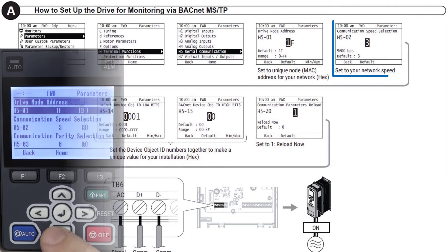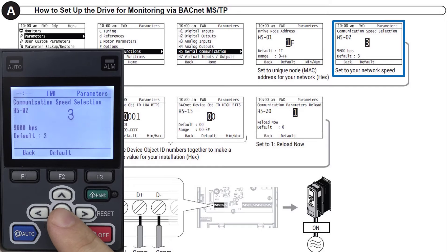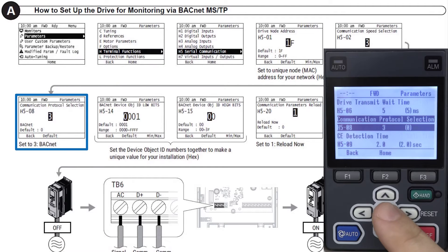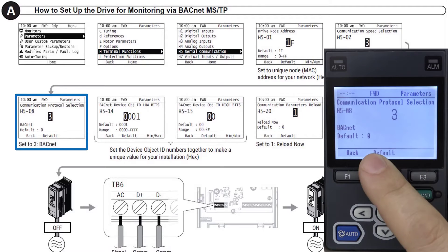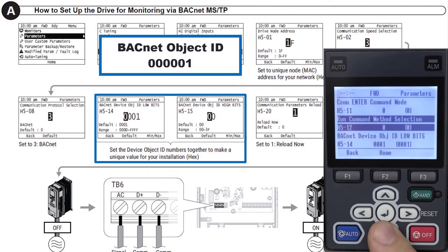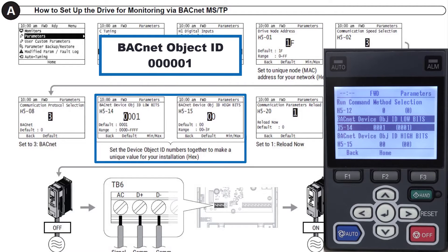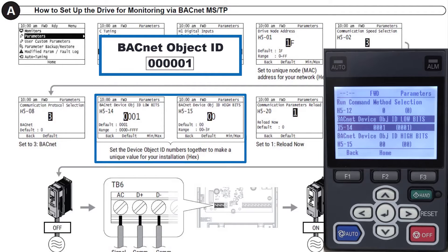Then verify that H5-02 communication speed matches the local network speed. Next, H5-08, the communication protocol, should be adjusted to 3 BACnet. Parameters H5-14 and H5-15 together form a BACnet device object ID for the Yaskawa product. Modify H5-14 to set the low bits and H5-15 for the high bits to create a unique value on the whole BACnet network.